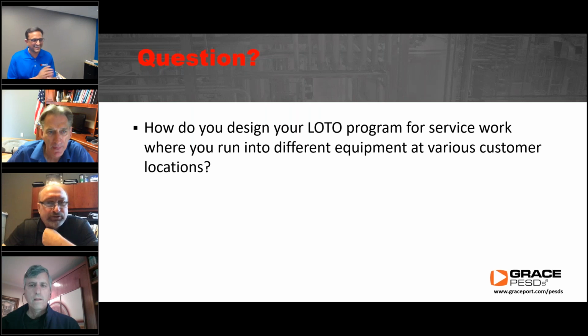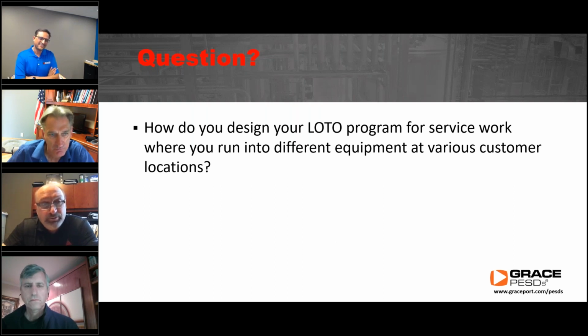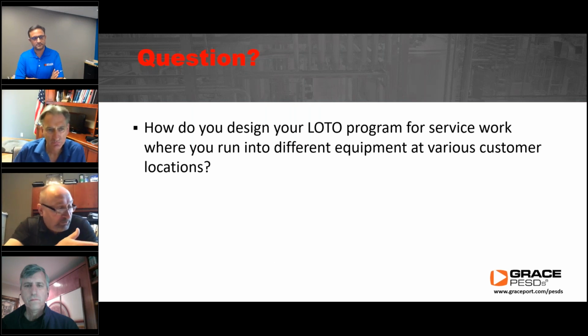If I can add to that — what you might find is that a client doesn't have any lockout tagout requirements, or it's very weak. So you better ensure your company's lockout tagout program meets or exceeds it, and in some cases, you may go to a site where the client doesn't provide any direction, or has limited direction. So you better ensure that, as the employer of the qualified persons doing electrical work in this case, your lockout tagout program — reviewing Article 120 again in NFPA 70E — follows the requirements of establishing an electrically safe work condition.